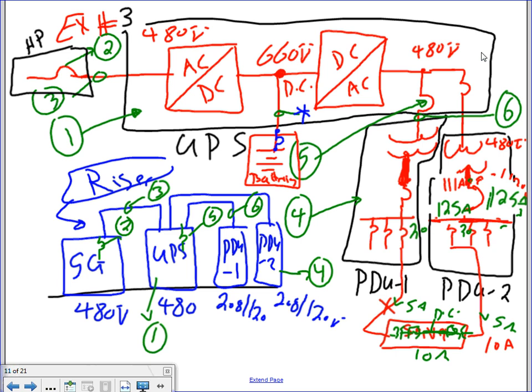Okay. So now, it has an AC to DC converter, which creates a lot of heat. That's why they have a dedicated cooling system to cool the UPS system. When you go to the data center of Allianz, you're going to see that they have CRAC units, computer room cooling units, basically an AC system, air conditioning, sitting in that room, cooling these computers. If you don't have them, and there's a situation where these fail, guys, literally, these servers, made out of non-metallic material like my computer, melt from the heat. These generate so much heat. Your laptop generates so much heat. That's why you have your fan there.